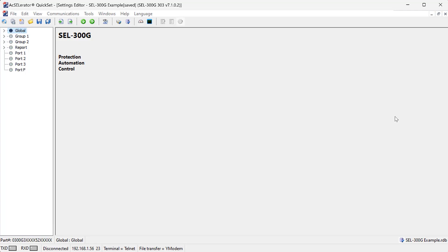Now let's move into the settings file. What I have here are basically default settings for an SEL 300G relay, which is one of the most popular generator protection relays here in the United States. There are a few settings to configure for our loss of field scheme. I'm going to focus only on the loss of field settings — in a real application you would need to configure all other settings as well. We start with the basic settings: PT ratio, CT ratio, nominal voltage, and nominal current. For this example I'm using the 492 MVA, 20 kV generator with CT ratio 3600:1 and PT ratio 167:1.